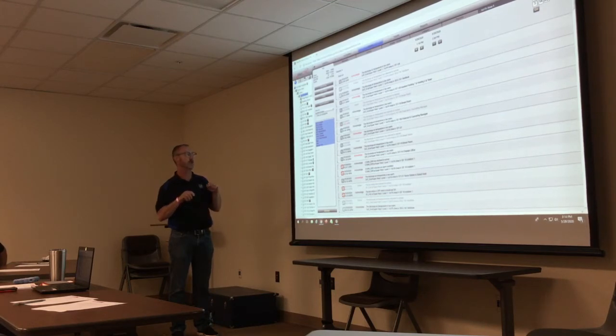Drop that down and let's do it by incident group. I had never used this one before, but I actually kind of like it because what it does is group together the two alarms. I should say the alarm and the return to normal. So at 2:45 and 10 seconds, the discharge air temperature was too warm on ST106, and 35 seconds later it returned to normal. So it grouped those, the alarm and the return to normal together. Here, where you don't see anything, the completion of the bracket, this guy is still in alarm.